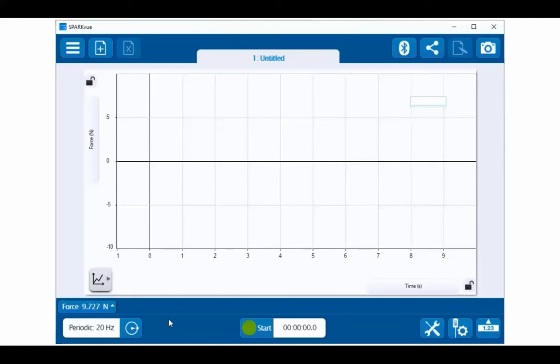When doing the calibration, please make sure that you have the fixtures that you'll be using for the work that you'll be doing. That way, any mass from these fixtures will be removed. Also, when you're attaching these fixtures, please make sure that you're monitoring the live data so that the attachment of these fixtures is not preloading the sensor in any way.